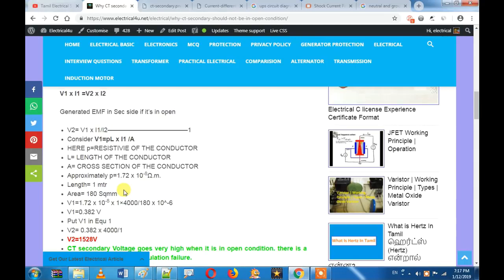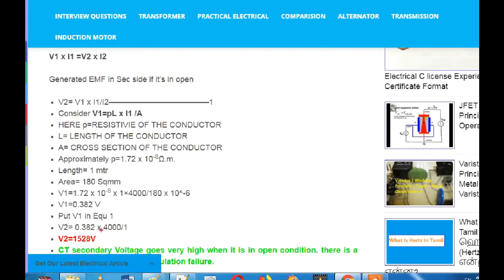If you open the CT load, we have to generate 1.5 kV. To avoid this dangerous voltage, what we have to do is short-circuit the secondary. When the secondary is short-circuited, the voltage is kept constant and under control.